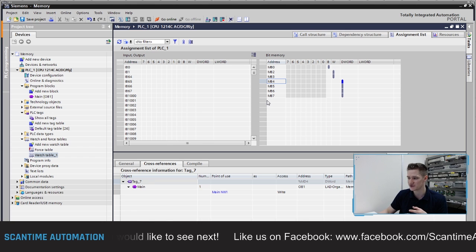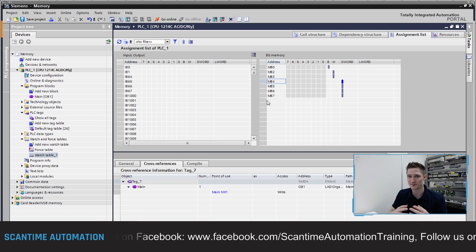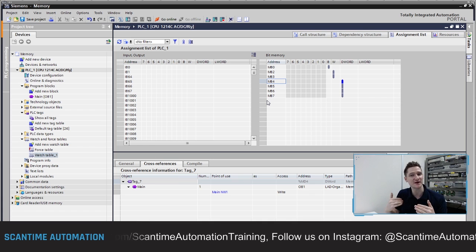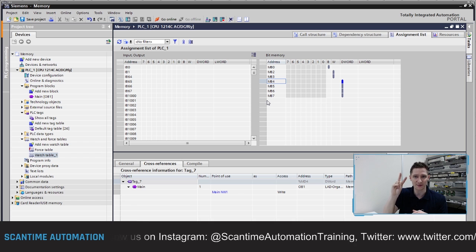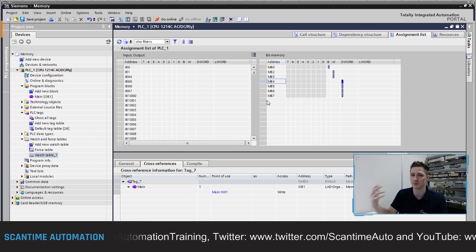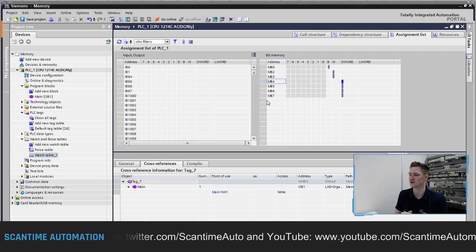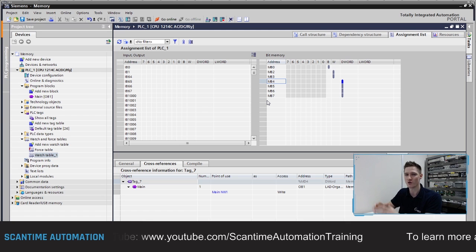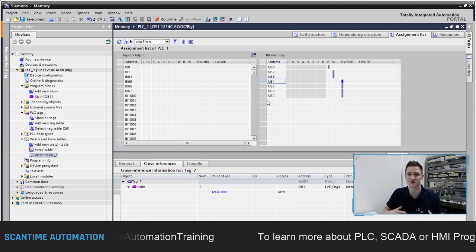A good rule of thumb when working with Siemens PLC programs using bytes, words, and double words: for bytes, go up in ones - MB0, MB1, MB2, MB3, MB4, MB5, etc. For words, go up in twos - MW0, MW2, MW4, MW6 - that way you're not overwriting anything. And for double words, go up in groups of four - MD0, MD4, MD8, MD12, MD16, etc.